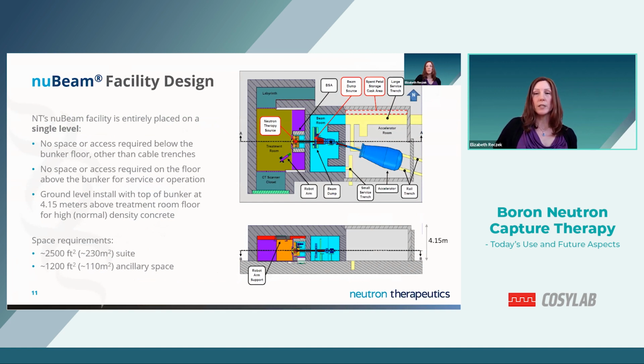A typical nuBeam facility is placed on a single level with no space or access required below the bunker floor or above the suite for service or operation. The facility requires a minimum height of just over 4 meters and has a footprint of 2,500 square feet or 230 square meters for the suite itself, with an additional 1,200 square feet or 110 square meters of ancillary space. Should supporting facilities be required for a standalone installation, these would be designed in conjunction with the hospital to suit their specific requirements and space constraints and can be located adjacent to, above, or below the nuBeam facility itself.